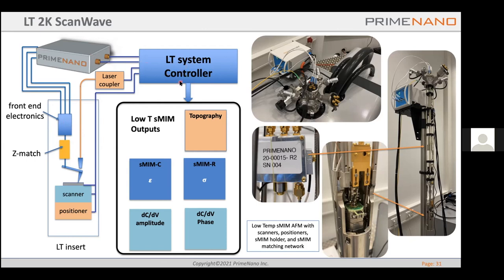In one scan, people can get topography, the sMIM C channel and the sMIM R channel, corresponding to permittivity and conductivity. People can also apply AC and DC voltage to get dC/dV amplitude and dC/dV phase. And the AFM itself uses a laser interferometer to detect the deformation of the cantilever. That's why you can keep a constant height or constant force to do the scanning and get the result.